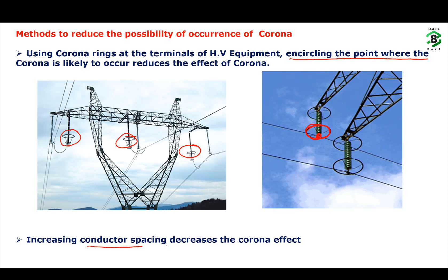In stormy weather conditions, if the number of free electrons in the air increases, the probability of occurrence of corona increases. In moist weather conditions, the ion density increases rapidly. That means in moist or stormy weather conditions, the number of electrons surrounding the conductor surfaces abnormally increases. Thus the voltage at which corona occurs reduces to 80% of the normal voltage. Therefore, the possibility of corona increases in rains, snowfall, and moist weather conditions.